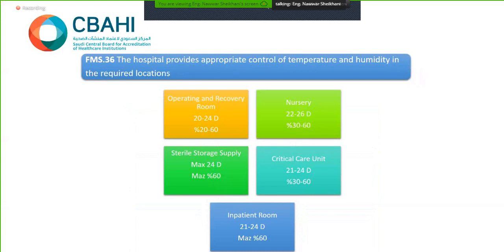Appropriate control of temperature and humidity: in operating and recovery areas, 20 to 24 degrees Celsius. In nursery, 22 to 26 degrees Celsius. In sterile storage supply, maximum 24. Critical care unit and patient rooms, 21 to 24. Overall, the hospital should be kept from 21 to 24.